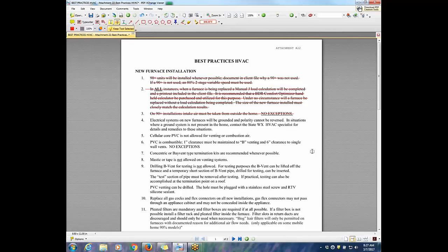So Matt's absolutely right. If you run across a 90% furnace that's not direct vented, which means that only the exhaust is going out to the outside and the intake is open to the house, it is now not a direct vent appliance. It falls under a mechanically drafted appliance, and yes, it can be backdrafted if you have a negative enough CAZ. And again, my contention is this: why would you ever do that?